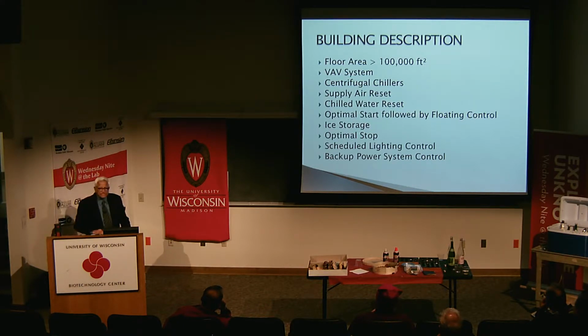And chilled water reset: if none of the cooling coils in the entire large building, which has several air handling units with several cooling coils, needs full cooling, maybe there is the opportunity now to raise the leaving chilled water temperature to a higher level. That means the differential head pressure in the chiller, between the evaporator pressure and the condenser pressure, is now smaller. That results in energy savings.